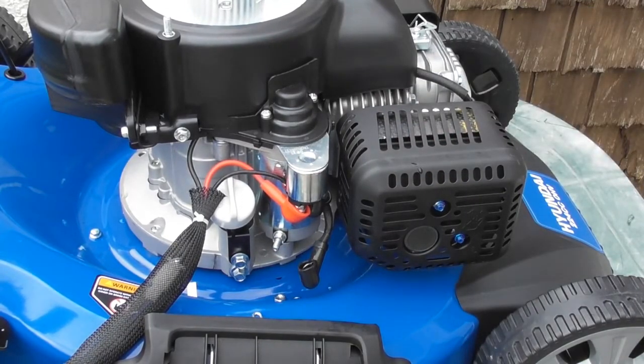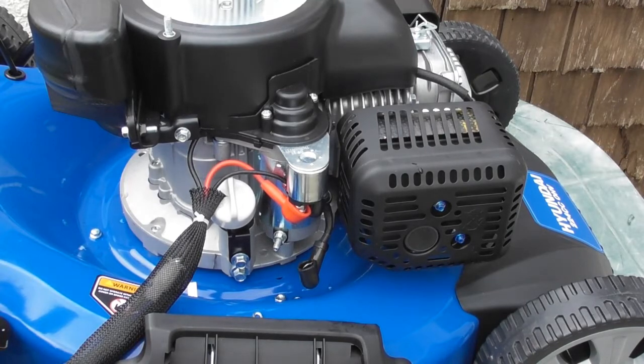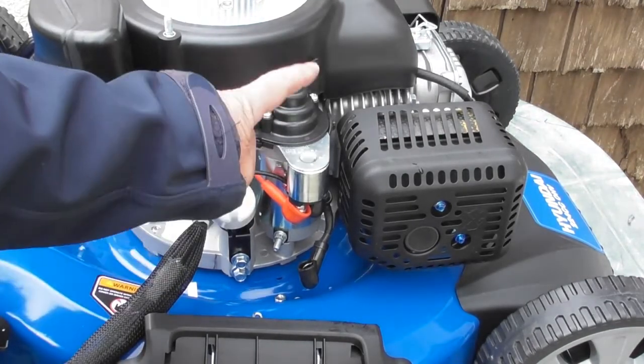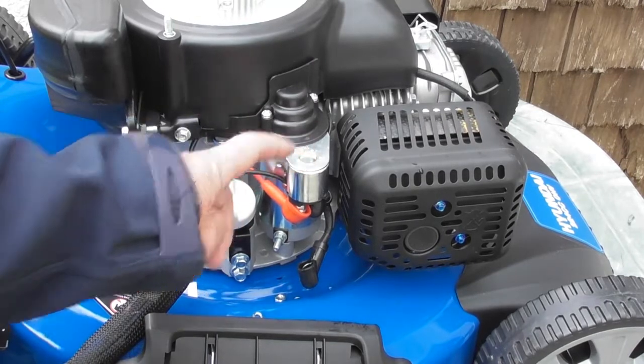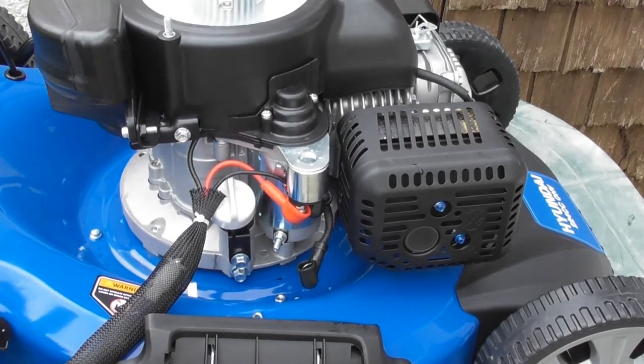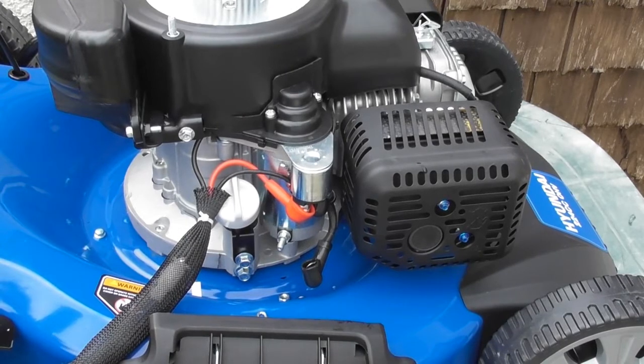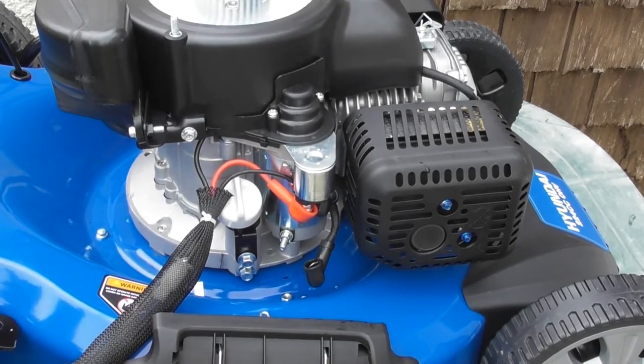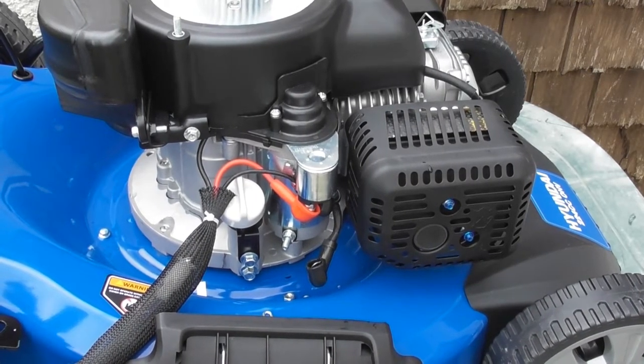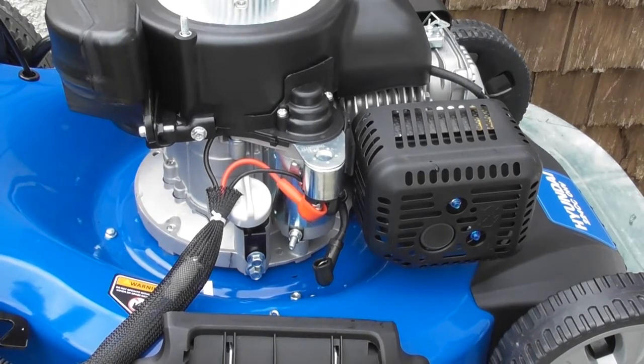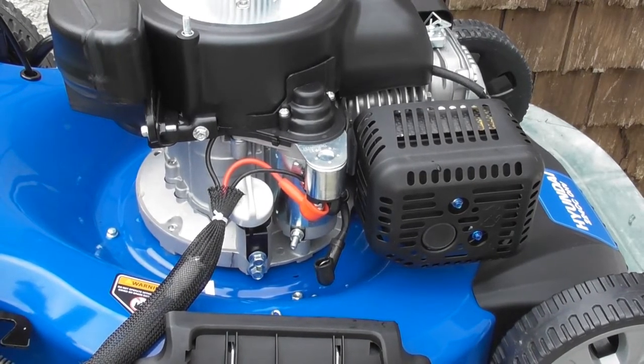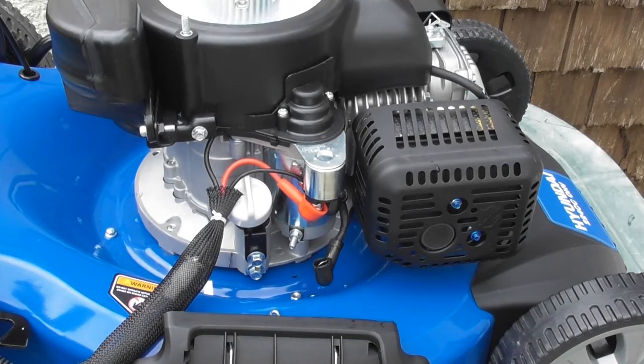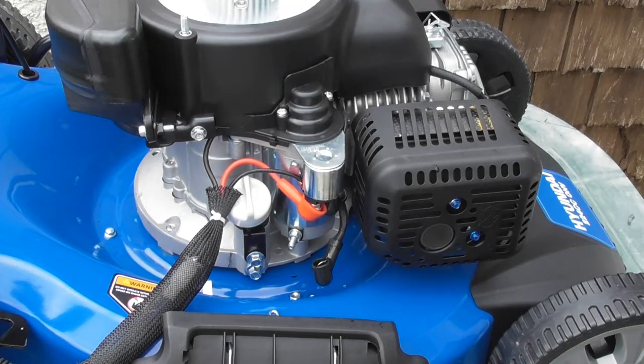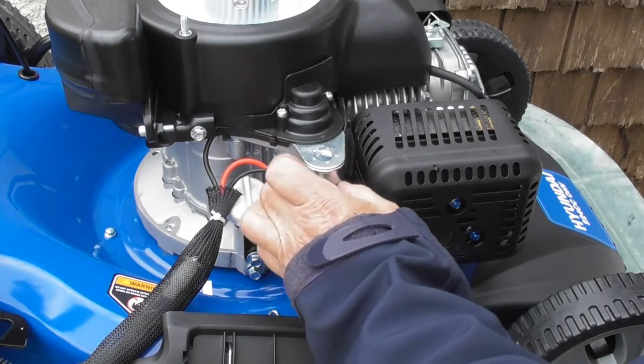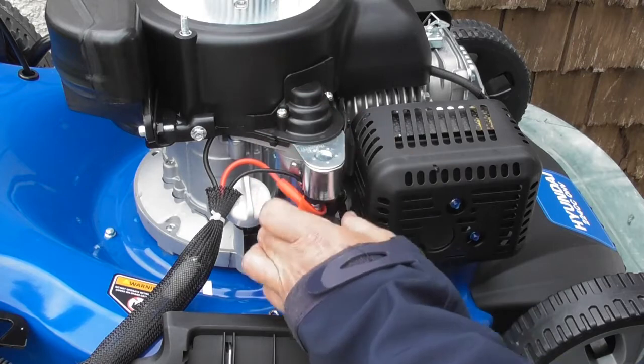So when I pull the OPC and push the start button, we should get an audible click out of the solenoid. Let's see. That first click is the OPC switch we talked about earlier. Now when I push the button, the solenoid is indeed clicking. Okay, so that's good news. That means the mechanical part of the solenoid, or the electromagnet, is working.